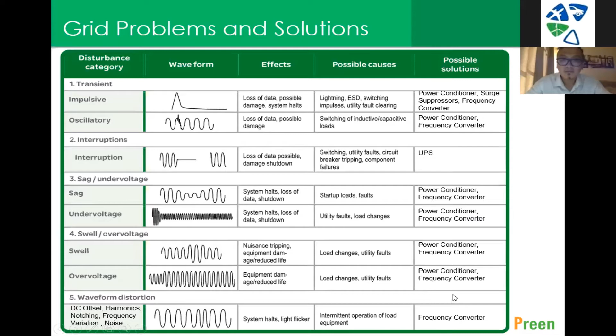For under voltage or over voltage, you can consider using a voltage regulator or power conditioner. But for distortion, you may not be able to use a power conditioner or voltage regulator - you may have to use a frequency converter. And when you have a problem with interruption or shortage, you may have to use a UPS. So different problems require different power solutions accordingly.